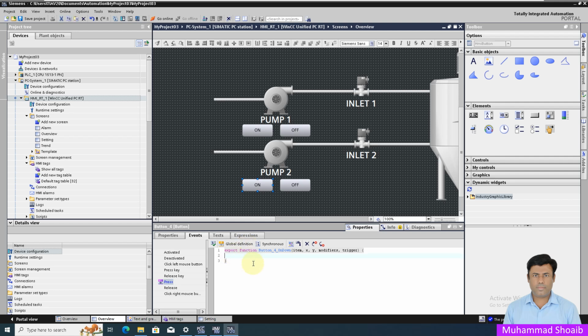Right here write HMIRuntime dot, select the tag, then system function dot SetBitInTag, and after that we will put our tag name.